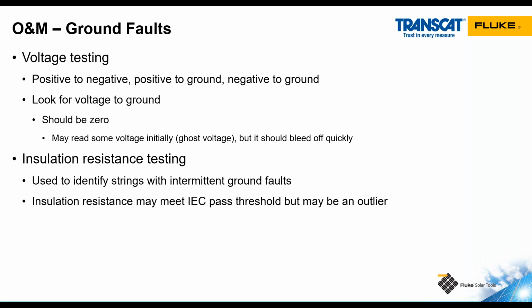The other test we can do is insulation resistance testing. And this is really helpful for finding strings that have intermittent ground faults. I can also do insulation resistance testing on circuits that are de-energized, like our PV output circuit from our combiner box to our inverter, or our inverter output circuit from the inverter to a point of interconnection, or even between different conductors in a circuit to find parallel arc faults. In some cases, I may have an insulation resistance value which is above the IEC standard, which in most cases is 1 mega ohm. But it may be different than other circuits.